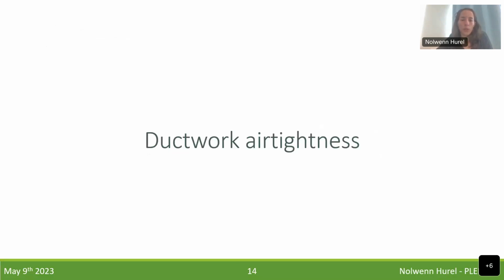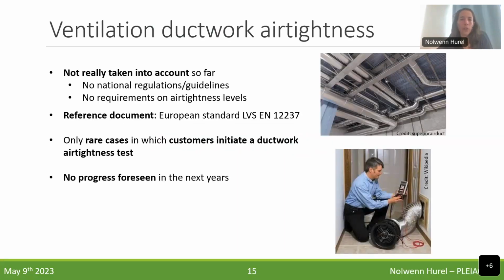And now a few words about the ductwork airtightness. This will be rather quick because the ventilation ductwork airtightness is not really taken into account so far in Latvia. There is no national regulation or guidelines. There are no requirements on airtightness levels to reach. The reference document is the European standard EN 12237. And there are rare cases in which customers initiate a ductwork airtightness test. So yes, only rare cases. And there is not really any progress foreseen in the next years.